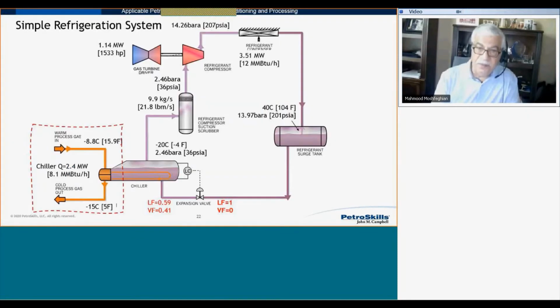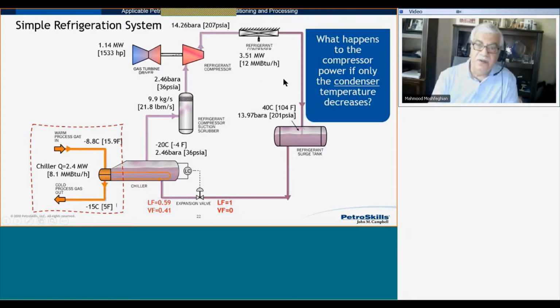Let's move on. So here, in this diagram, I put the numbers with the equipment so you can follow, like the power requirement for compressor, 1,533, and so on. Now, let's see how we can reduce the power requirement. What happens to the compressor power if only the condenser temperature goes down? If the condenser temperature goes down, the condensing pressure goes down, the discharge pressure goes down, so the power requirement goes down.